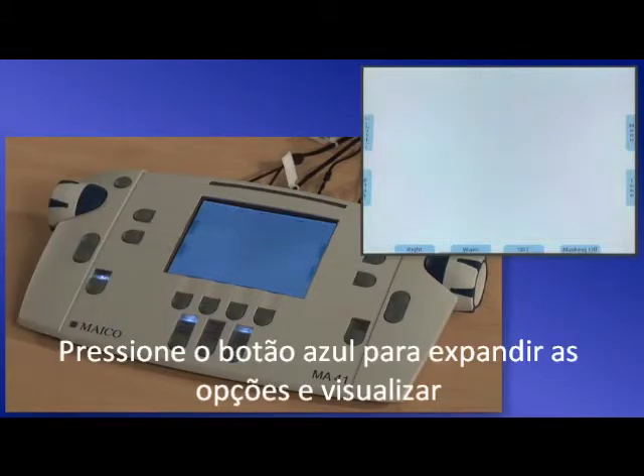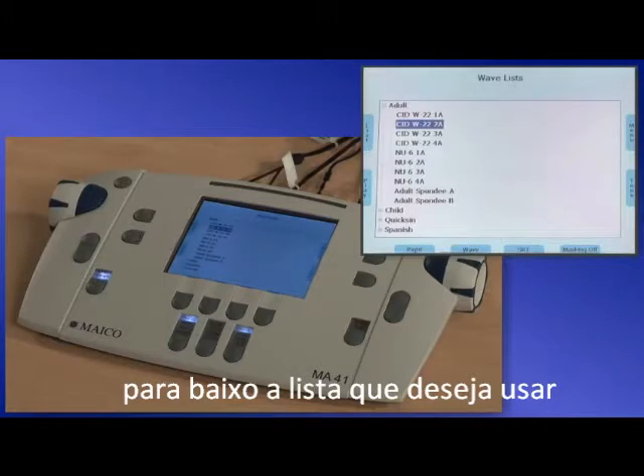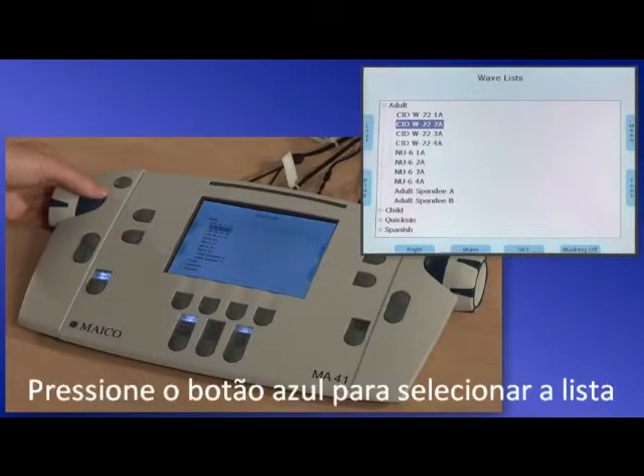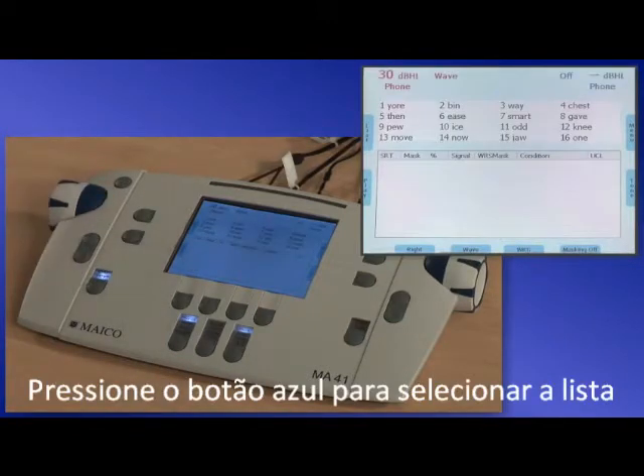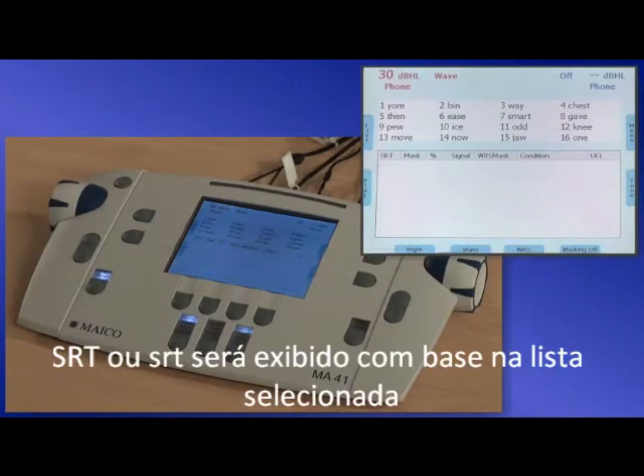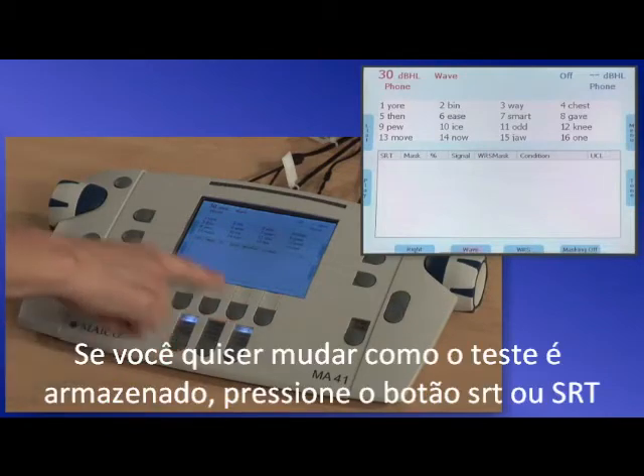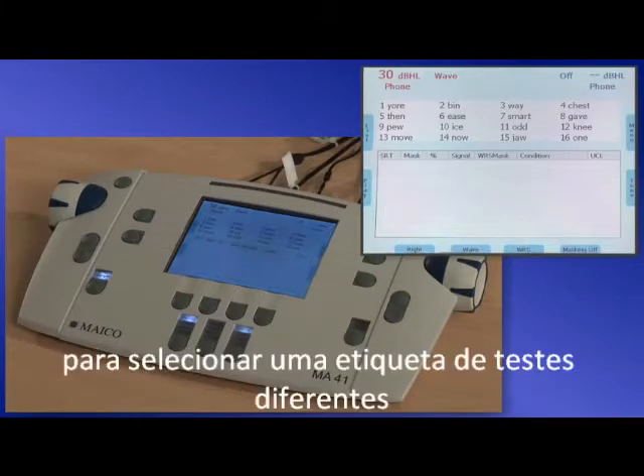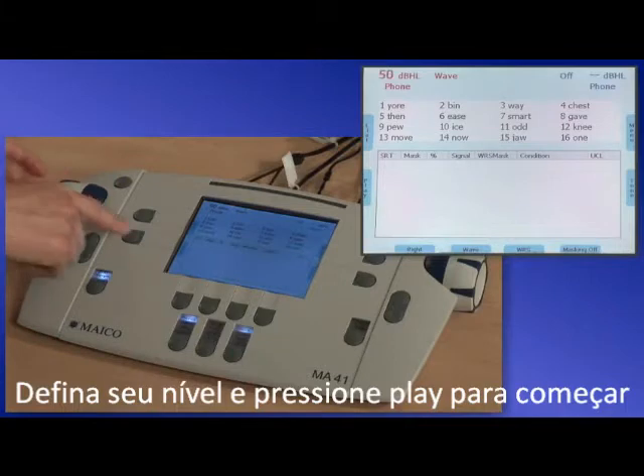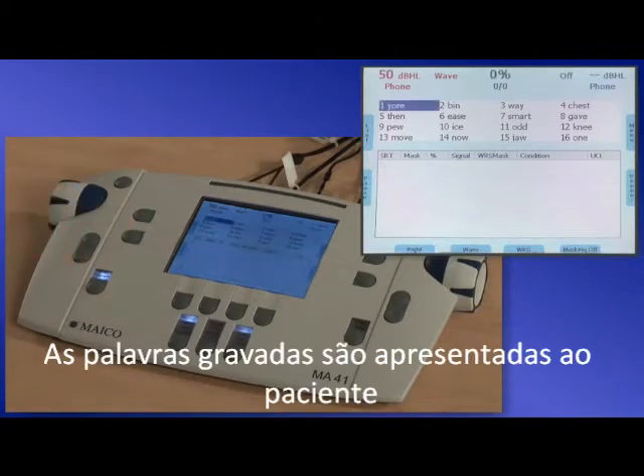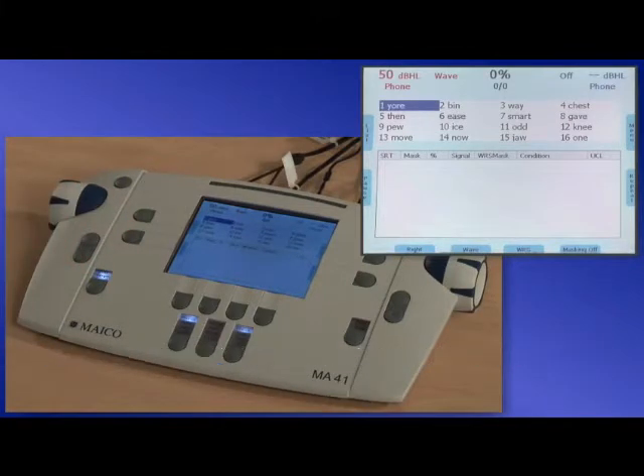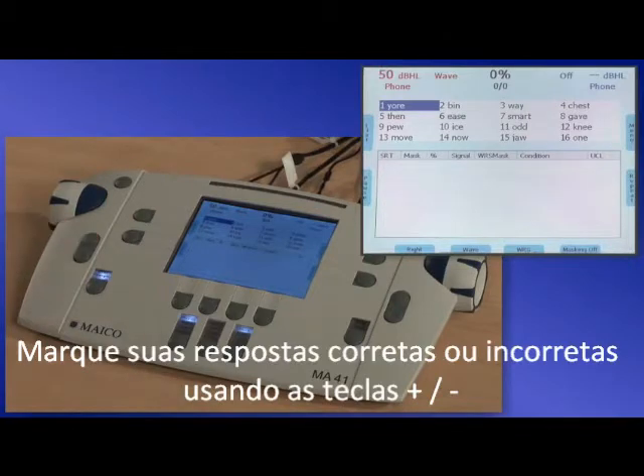Press the blue button to expand the selections and dial down to the list you would like to use. Press the blue button to select the list. SRT or WRS will be displayed based on the list that you selected. If you would like to change how the test is stored, press the WRS or SRT button to select a different test label. Set your level and press play to begin. The recorded words are presented to the patient. Score their responses correct or incorrect using the plus or minus keys.